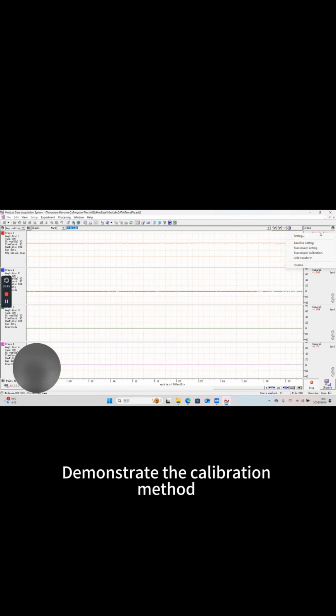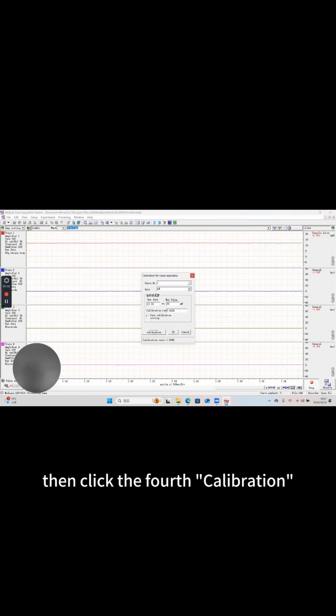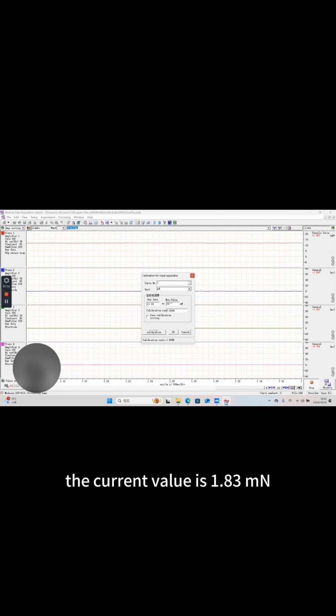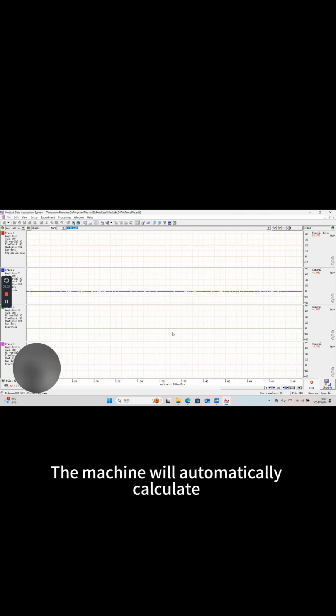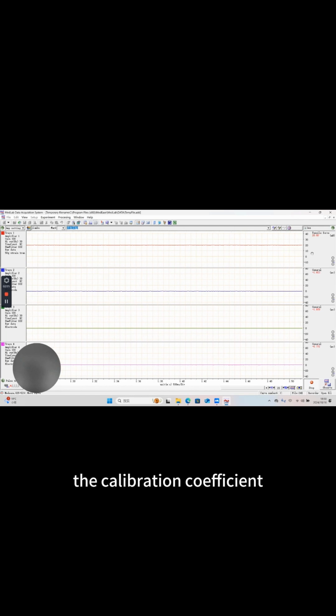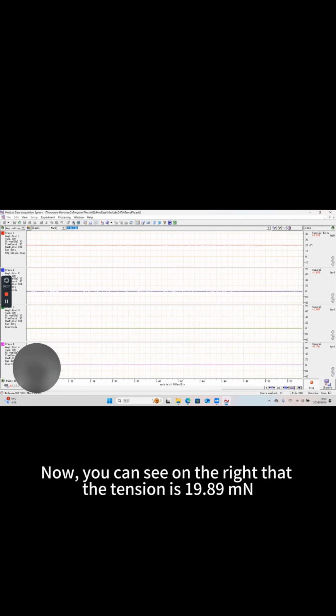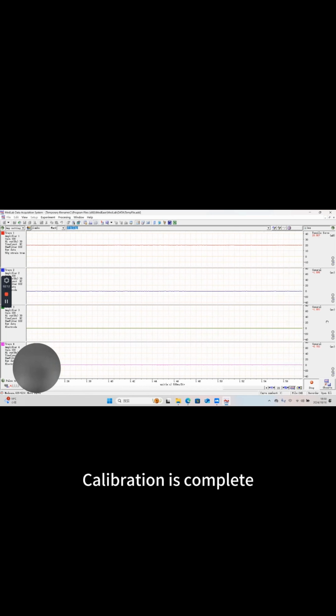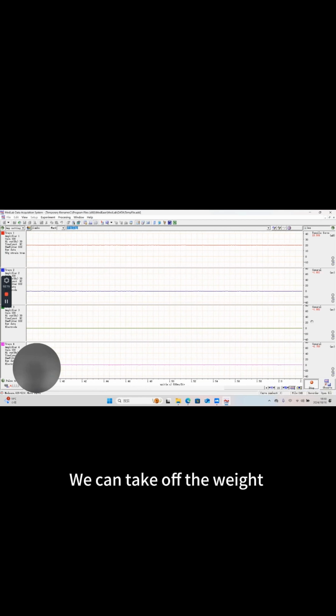Now demonstrate the calibration method. Click Setting, then click the 4th Calibration. The current value is 1.83 mN, and we are using a 2-gram weight, which corresponds to 20 mN. Enter 20. The machine will automatically calculate the calibration coefficient. Now you can see on the right that the tension is 19.89 mN. Calibration is complete. We can take off the weight.